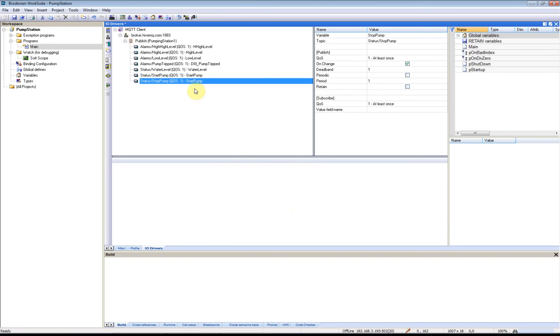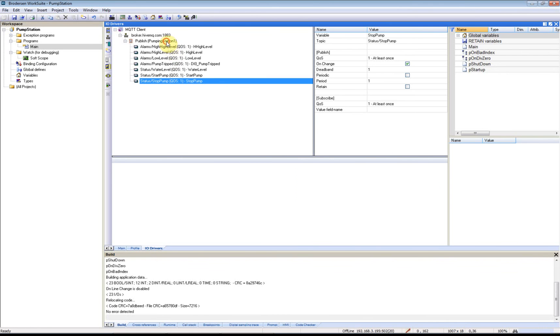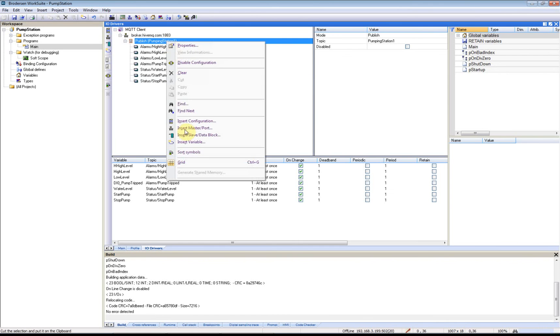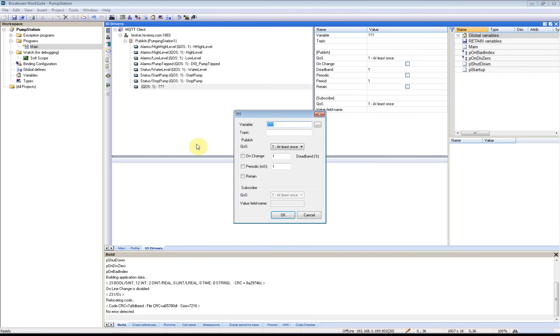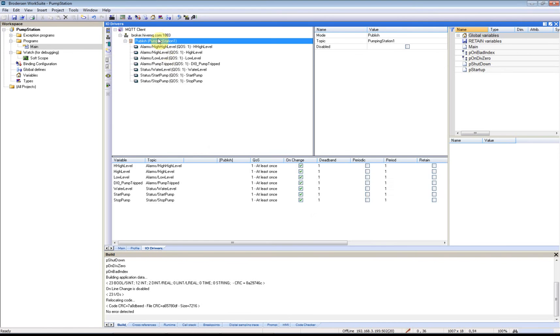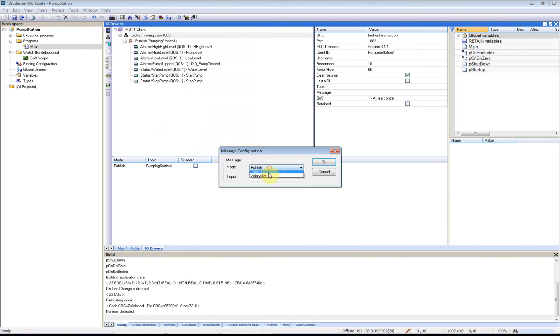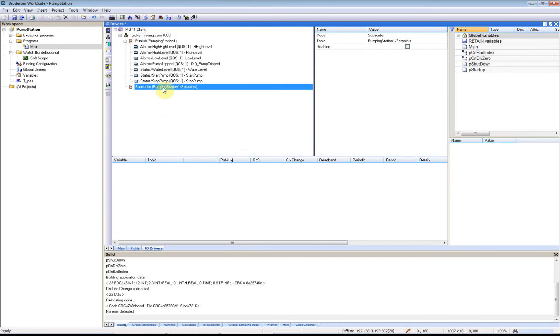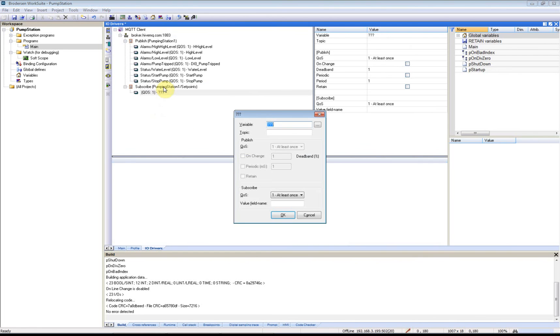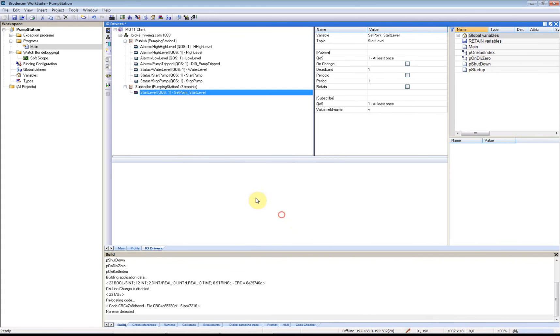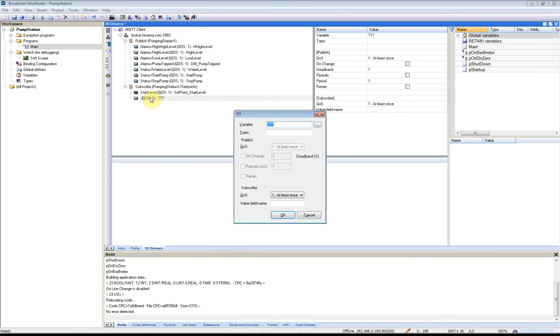So these are the events that I will publish to the MQTT broker. Now I'll subscribe to some messages that other MQTT clients can send to us. This is done by subscribing, and it will be PumpingStation1/SetPoints. I'll add one for Set Point Start Level, looking for the value in the value field V, and one for Set Point Stop Level.